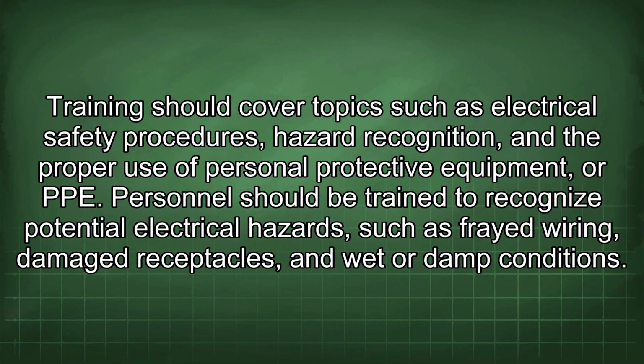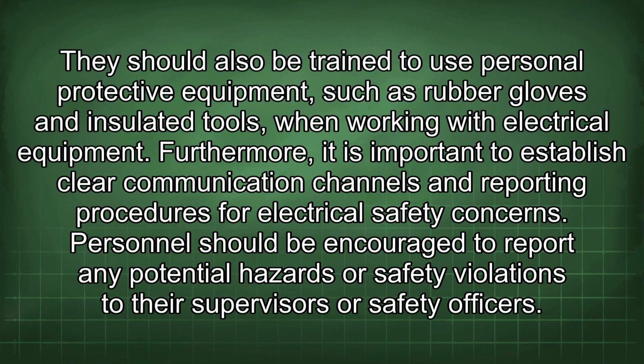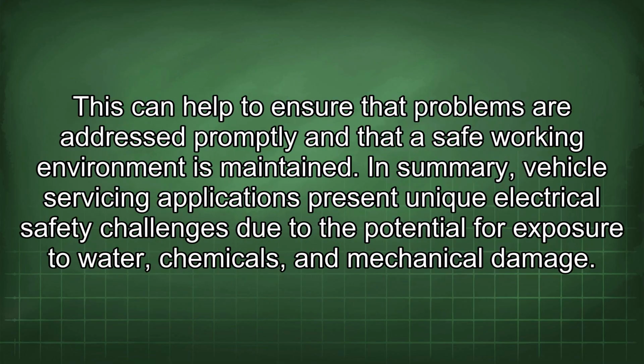Personnel should be trained to recognize potential electrical hazards such as frayed wiring, damaged receptacles, and wet or damp conditions. They should also be trained to use personal protective equipment, such as rubber gloves and insulated tools, when working with electrical equipment. Furthermore, it is important to establish clear communication channels and reporting procedures for electrical safety concerns. Personnel should be encouraged to report any potential hazards or safety violations to the supervisors or safety officers. This can help to ensure that problems are addressed promptly and that a safe working environment is maintained.